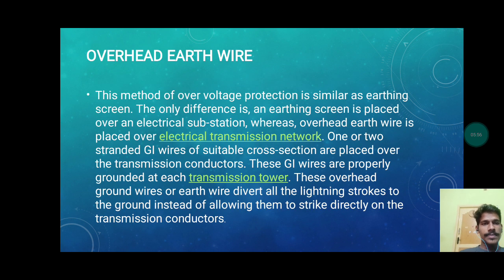And next one is overhead earth wire. The method of over voltage protection is similar to the earthing screen. The only difference is that an earthing screen is placed over an electrical substation, whereas an overhead earth wire is placed on the overhead electrical transmission network. One or two stranded GI wires of suitable cross section are placed over the transmission conductors. These GI wires are properly grounded at each transmission tower. The overhead earth wires divert the lightning strokes to the ground, which would otherwise strike directly on the transmission line conductors.